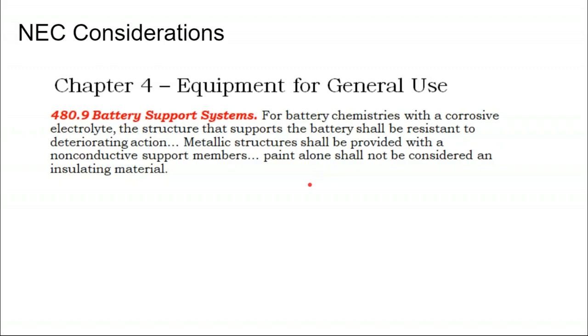Here's another one for planning. Let's say you plan on just putting these heavy batteries down on the floor. The support structure for the batteries cannot be conductive, and concrete is considered conductive, and a metal shelf is considered conductive. So if you're setting the batteries directly down on concrete or directly onto a metal shelf, you need to put a padding down, like a rubber padding, for them to sit on top of.